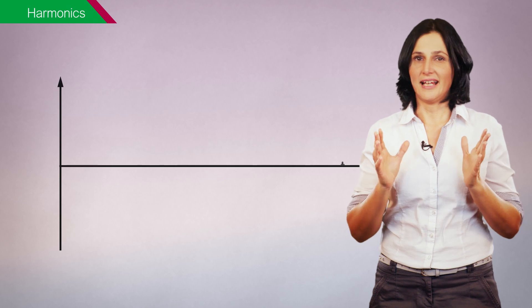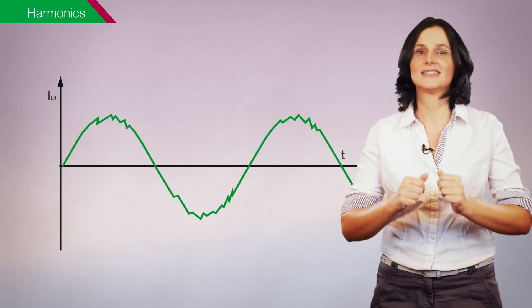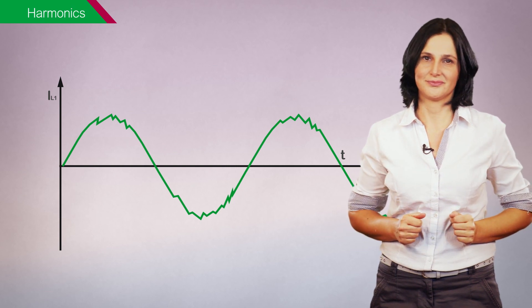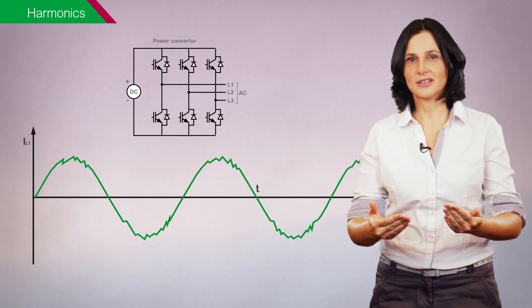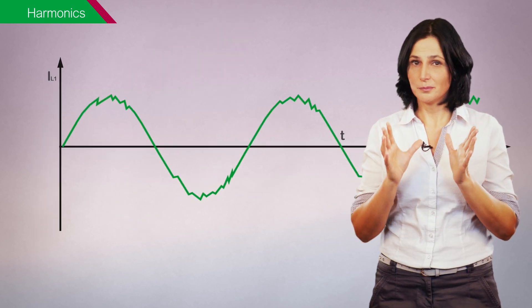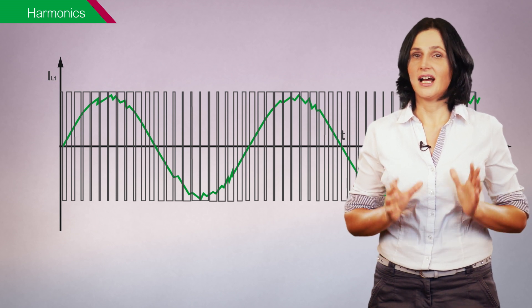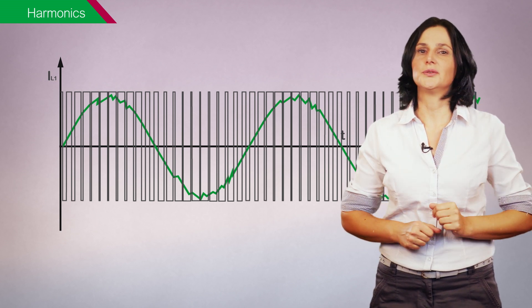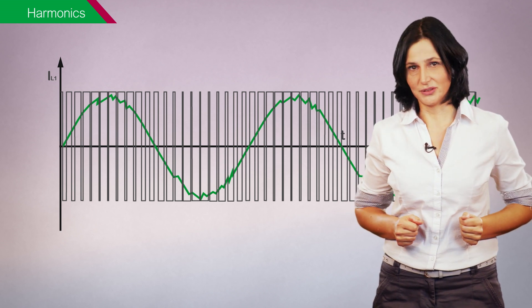Another potential disturbance is harmonic distortion. Like all electronic equipment, photovoltaic inverters inject harmonics into the electrical installation. Photovoltaic inverters convert DC power into AC by using pulse-width modulation switching. This method allows control of the magnitude and frequency of the inverter output but generates high-frequency harmonics.